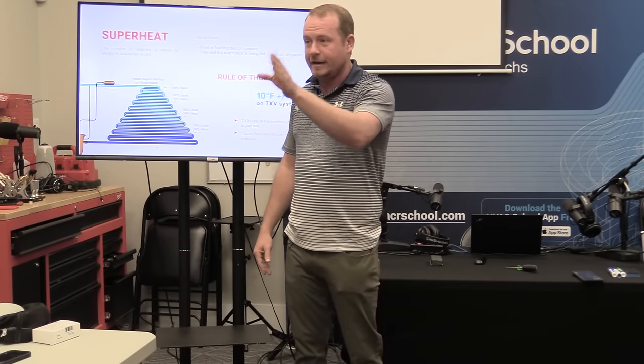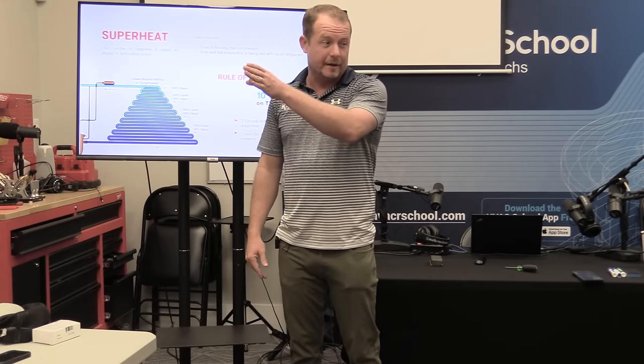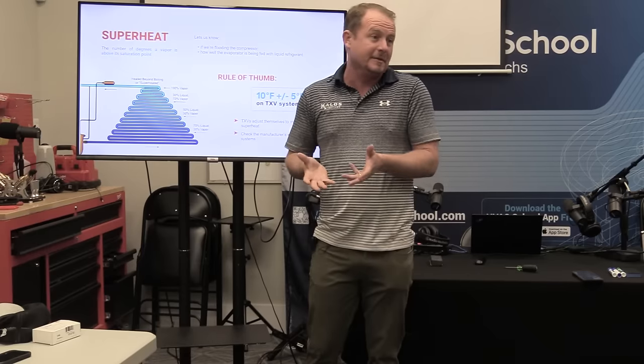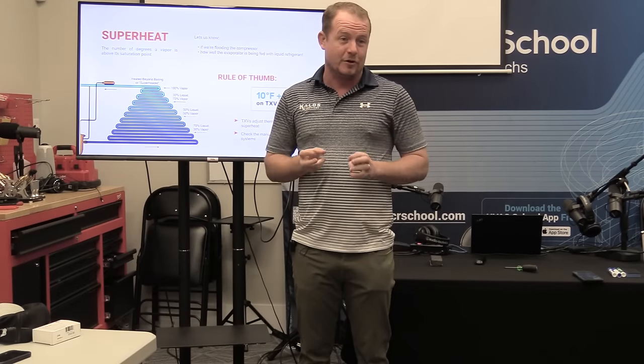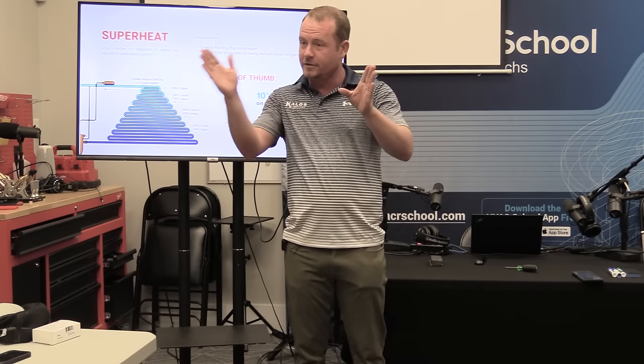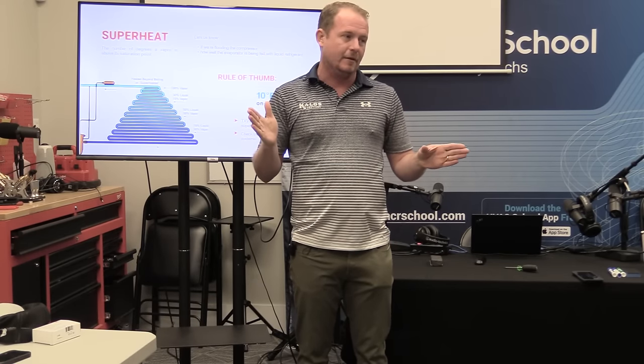As an installer, in most cases other than airflow, those things are going to be in line because it's brand new equipment. Generally speaking, you get the subcool right and you're in good shape. That's also why you follow the weigh-in guidelines — you're not just guessing. You're using a lot of different data points. But if everything looks good and one data point is way off, question the measurement itself. Usually when it's something wrong with equipment, you're going to have more than one data point showing off.